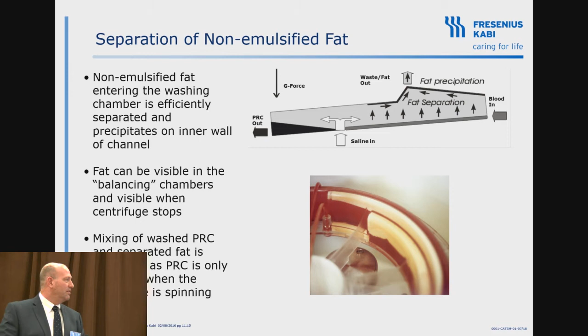So the fat, because it's the lightest, comes out first, and it goes into a part of the chamber called the balancing chambers. And they put those in there when they first designed the chamber to balance it when it spun for the weight. And when they started playing with it, they realized all the fat was being collected in there. So we're collecting the fat and separating it by the specific gravity. We're not washing it out.